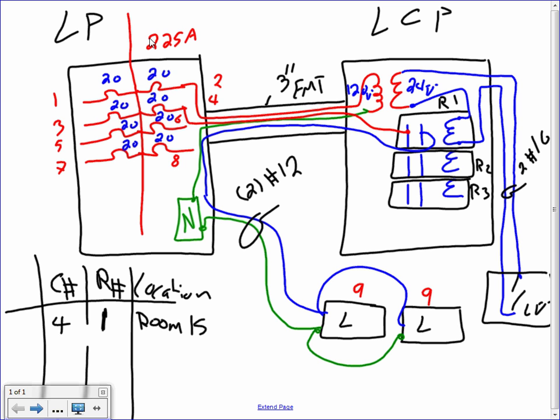Can I have a thumbs up, Chad, that we fully understand that one? So you can imagine if this was a low voltage switch or occupancy sensor, almost identical. There's a power pack, some call it power pack, but the occupancy sensor interface is almost similar. You have a sensor here that senses movement, closes the contact, and instead of you flipping the contact closed, the sensor will close the contacts. When you close the contact, you bring 24 volts across the coil, it will energize, shut that contact, and that light is up and running.